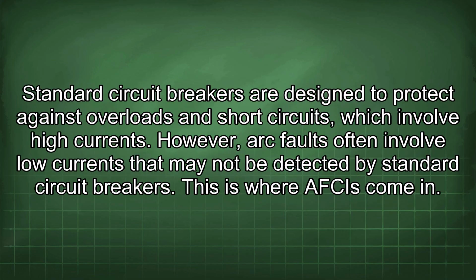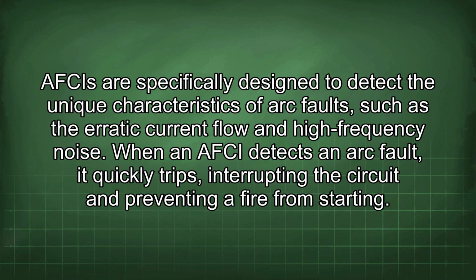Standard circuit breakers are designed to protect against overloads and short circuits, which involve high currents. However, arc faults often involve low currents that may not be detected by standard circuit breakers. This is where AFCIs come in. AFCIs are specifically designed to detect the unique characteristics of arc faults, such as the erratic current flow and high-frequency noise. When an AFCI detects an arc fault, it quickly trips, interrupting the circuit and preventing a fire from starting.